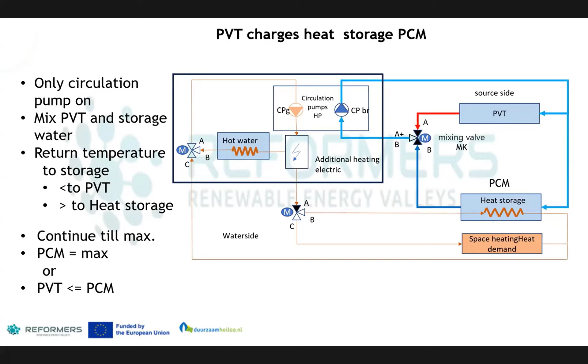In case the temperature of the PVT is too low to directly charge the PCM storage, it is possible to do this using the heat pump. Suppose it is 11 degrees during the day, which is too low for charging the PCM tank, but in the night it is below 0 degrees. Then you can use the energy in the 11 degrees in daytime by increasing it by the heat pump so that the storage can still be charged and can be used in the night when it's 0 degrees. This is then a kind of cascade system. The product, the heat at night, is achieved in two phases. First, by filling the storage with favorable temperatures during the day, and second, use this intermediate product energy in the night.